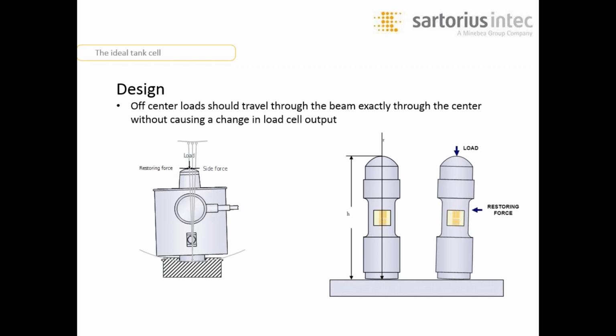The canister style load cell. It's the earliest load cell design. It's either hermetically sealed or welded to protect the gauges. There are two types of canister construction: single column, which is what you see here, and multiple column. Single column canisters cannot normally withstand a side load of over 15%. Multiple column canisters can withstand more side load than the single column variety.